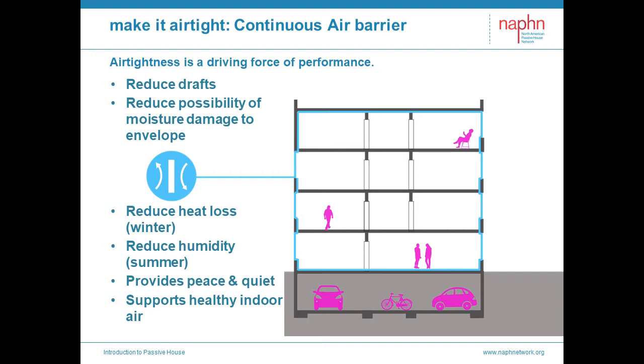Let's talk more about why air tightness is so important. It profoundly affects so many fundamental aspects of building performance. We've spoken about it supporting indoor air quality. What about comfort? It eliminates those annoying drafts — drafts we need to overcome with large mechanical systems, more brute force treating symptoms. Air tightness also protects the enclosure from moisture damage. It is not generally well understood that air moving through enclosure leaks can carry massive amounts of moisture, producing rot and mold, and is a leading cause of building damage insurance claims. By making the enclosure more airtight, we reduce moisture damage risk and increase durability.